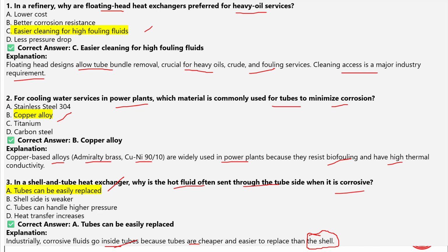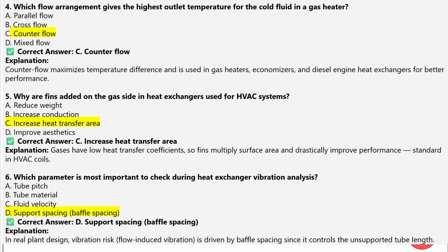Moving on to the next slide. In this slide, which flow arrangement gives the highest outlet temperature for the cold fluid in a gas heater? So the answer is counterflow. So what does counterflow do? Counterflow maximizes temperature difference and is used in gas heaters, economizers, and diesel engine heat exchangers for better performance.